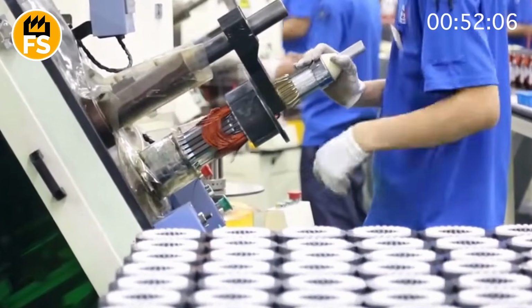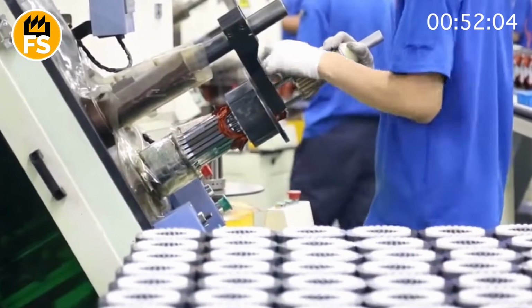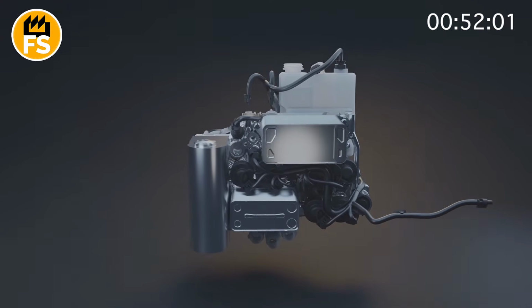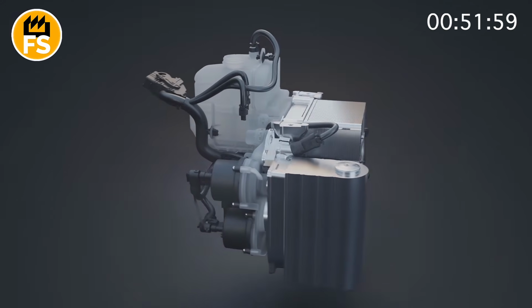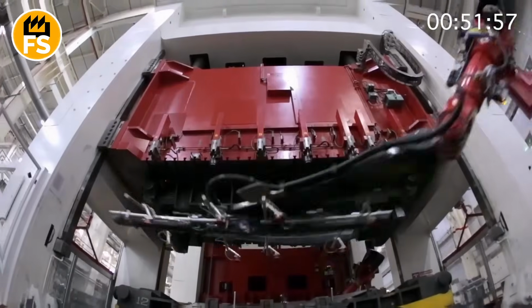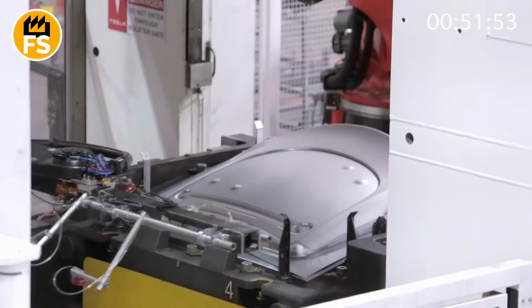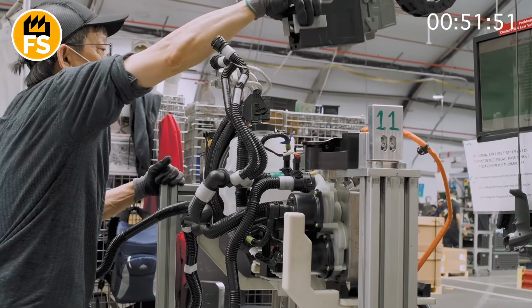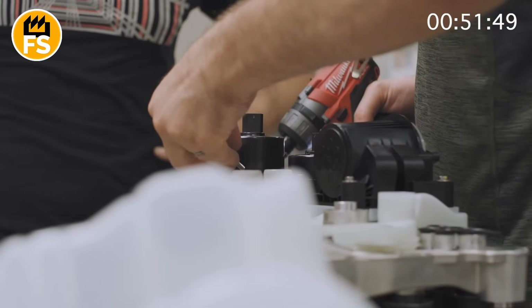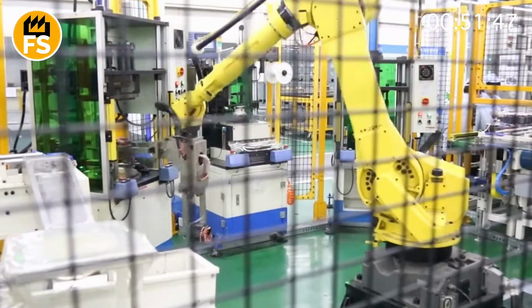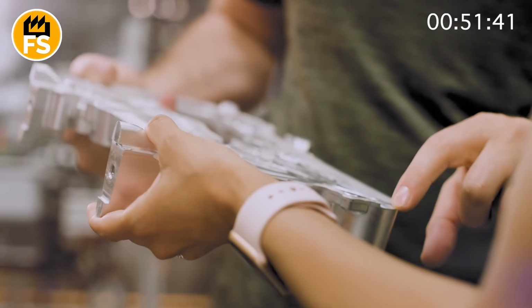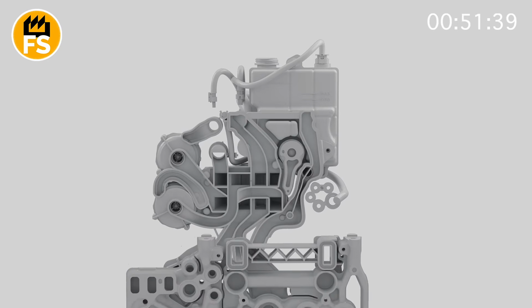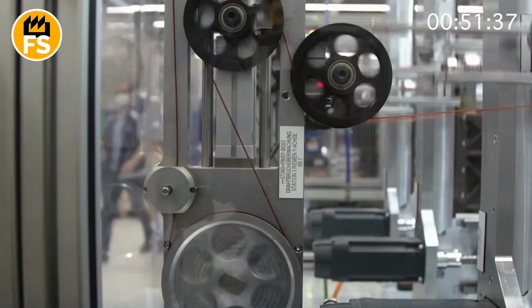The result? A compact, shiny cylinder with windings of copper wire or closed bars. It will be inserted into the stator, and the magic of converting electricity into motion will become possible. It all starts with checking dimensions and tolerances. The gap between the rotor and the stator, the so-called air gap, must be very small. If it's too narrow, friction will occur. If it's too wide, the magnetic field will be weak, and the motor will lose efficiency.